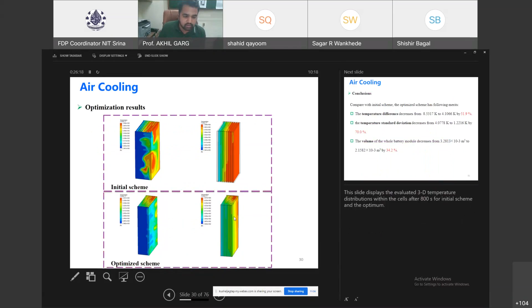Comparing the initial scheme with the optimized scheme on the following metrics: temperature can be reduced by 71%, temperature standard deviation can be reduced by 70%, and the volume can be reduced by 34%. So similarly, we follow the same methodology or schematic for liquid cooling.